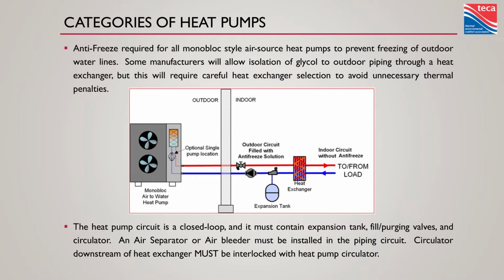I don't care if it's CFM or GPM, exact same thing applies in air-to-water heat pumps. We're moving more flow to transfer the same amount of heat, just a shorter temperature rise. That's critical to understand because people get into a habit where I'm hanging a 50,000 BTU boiler on the wall, I can run this in this size piping and use this size pump, and you start talking heat pumps and you start talking glycol, and you are going to have a system that will not last as long as its warranty, unfortunately. So on top of that, you're crippling its capacity, you're crippling its efficiency.